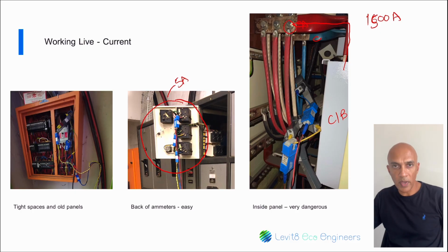Now in order to do a measurement here, it becomes quite difficult if your CT cannot go around this bus bar. And also if your CT ratio is a maximum of 1,000 amps, then you have a problem. However, if all these outgoing feeder cables are the same size, and you've got to make sure that they are the same size, then you can connect to one of the feeder cables, and then in your ratio, you multiply your ratio by 3.